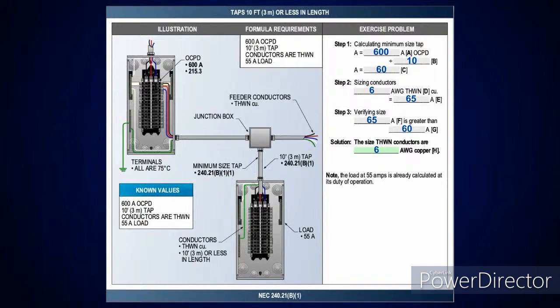1B1. And as I said, and I'll rephrase this one more time, if you're doing a tap that's 10 foot or less, you divide by 10. All other taps you take at a third that are greater than 10 foot. And then if you have a transformer and a tap, you do the secondary to third or the primary to third. But when you get to the secondary, you're going to take it at a third, but you also need the ratio of the transformer. Okay. So we'll go through this real quick. This shouldn't take long. Everybody should have these taps down pretty well now.